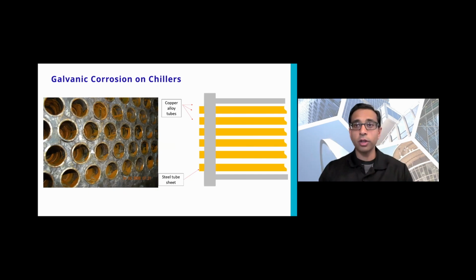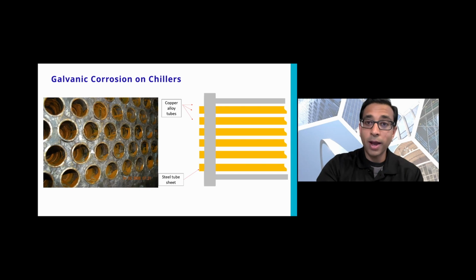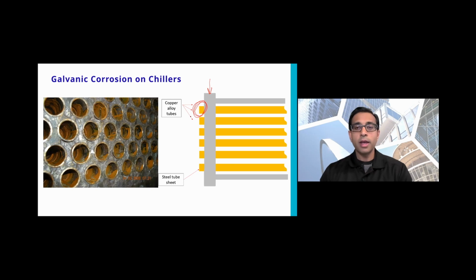All right, so let's talk a little bit about galvanic corrosion. Why does galvanic corrosion happen on a chiller system? Well, it's very simple. You've got two metals and they're not the same metal. They're dissimilar metals, right? So you have the carbon steel tube sheet, which is the gray area, and you have the copper alloy tubes, which is the yellow area. And so this is where you're going to have your potential issues when it comes to galvanic corrosion.